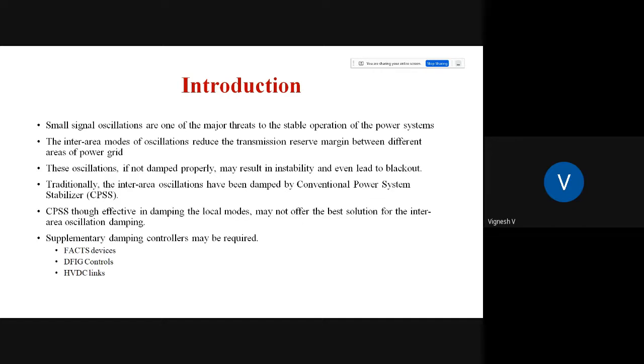To reduce small signal oscillations, we typically use conventional power system stabilizers, which we call CPSS. The CPSS are effective in damping the local modes, but for inter-area types of oscillations, CPSS may not be effective. So we need to use some supplementary damping controllers, which should be wide area, to damp out these inter-area oscillations.